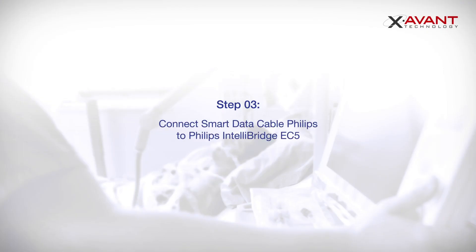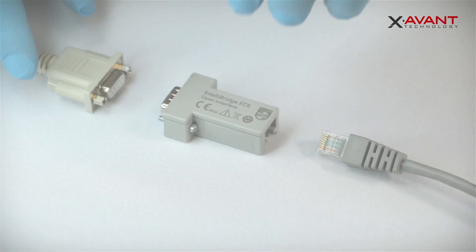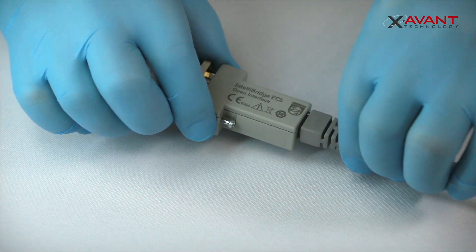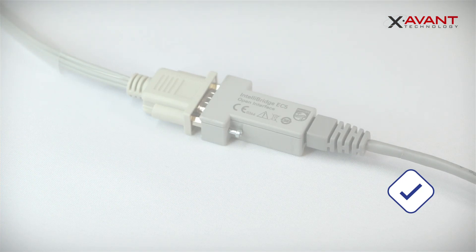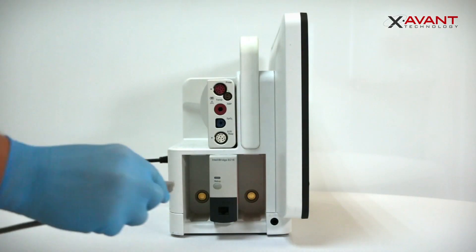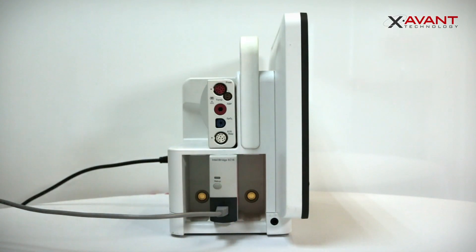Connect the Smart Data Cable Philips to the Philips IntelliBridge EC5 Module using the RS232 connector. Also connect the connection cable to the EC5 Module. Then connect the Philips EC5 Module to the Philips EC10 Module using the RJ45 Connection Cable.